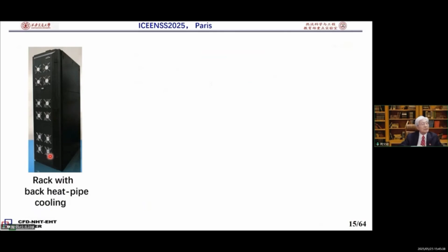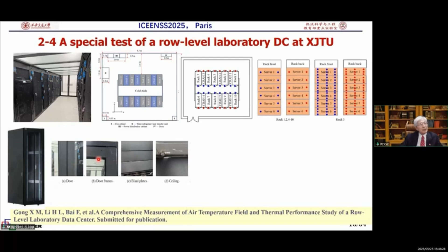Now I will give you a special test result of a row-level laboratory data center at our university. We have a row-level laboratory data center with 10 racks and 6 air conditioners. We set thermocouples in front of the rack and at the back of the rack, many at both locations. We also checked all the leakages for air leakage, because in the rack there are many places where air may leak. So we sealed the leakages.